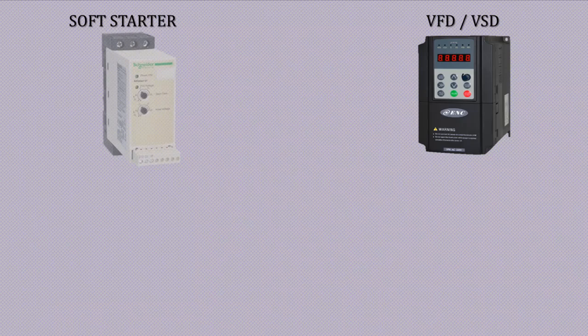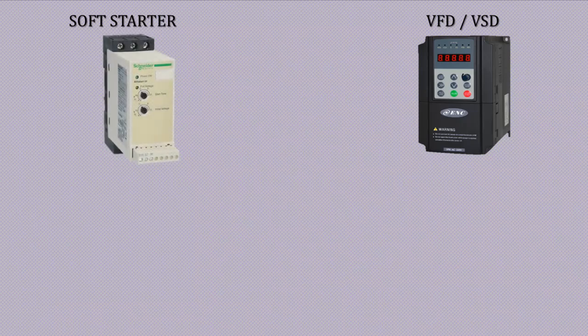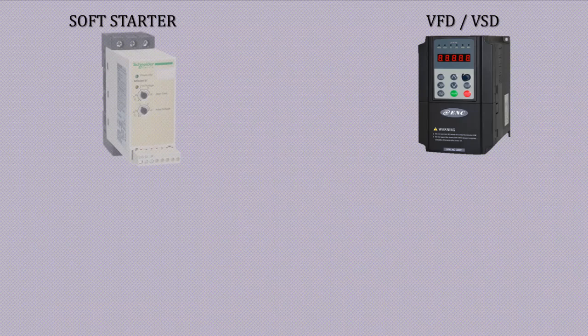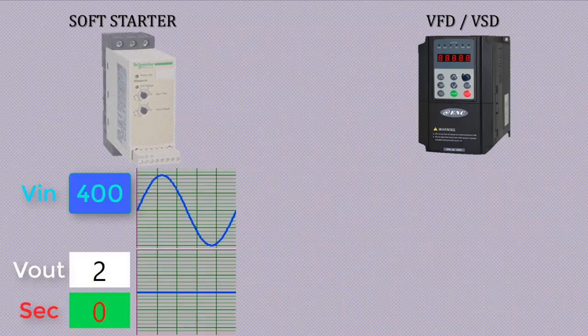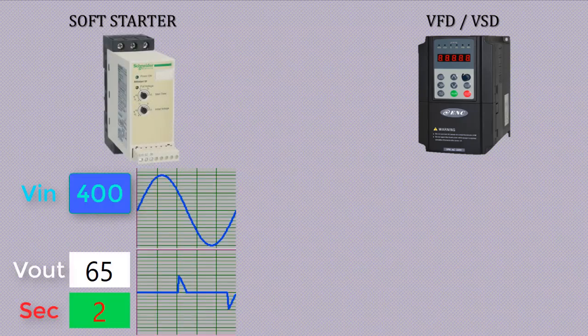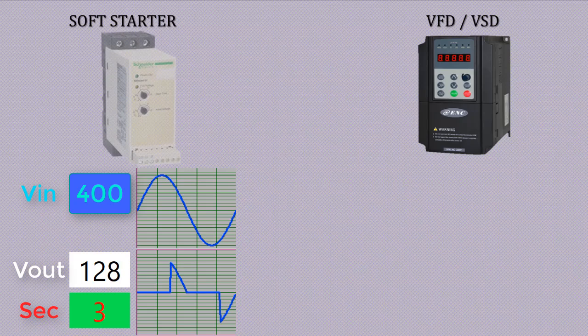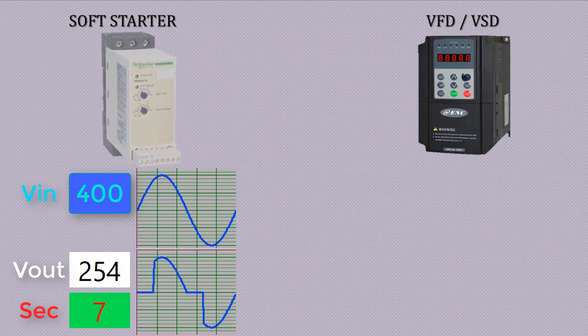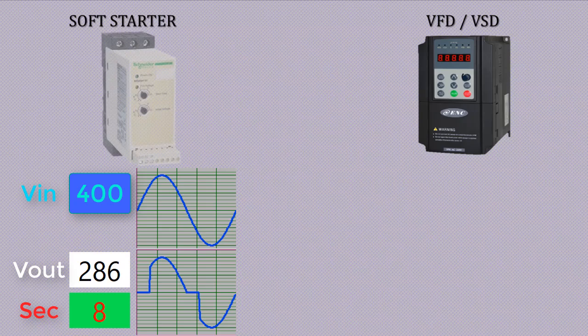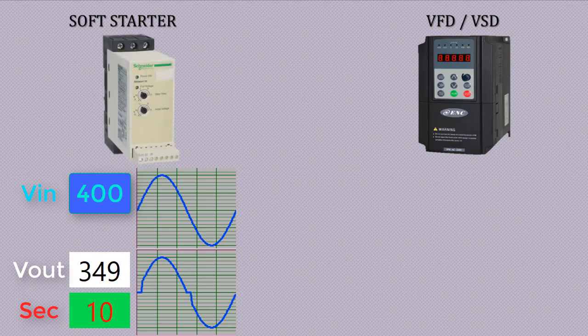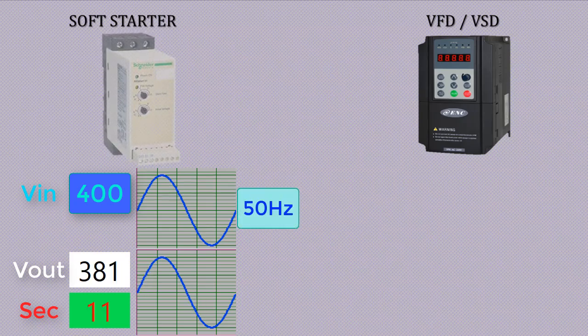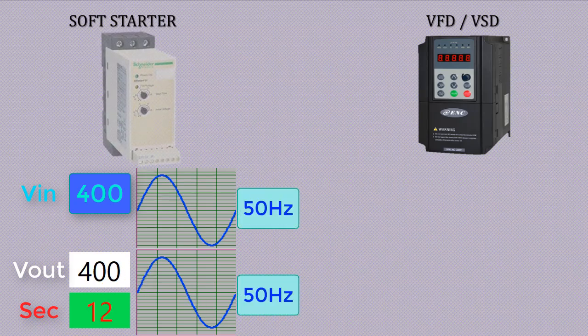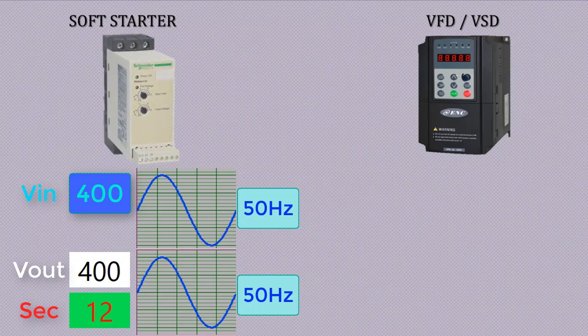If we set acceleration time 12 seconds in soft starter and initiate start command, then output voltages are increased from zero to rated voltage in 12 seconds by varying the firing angle across thyristors as shown in this waveform. The main point is output frequency will remain 50 hertz throughout the acceleration period.